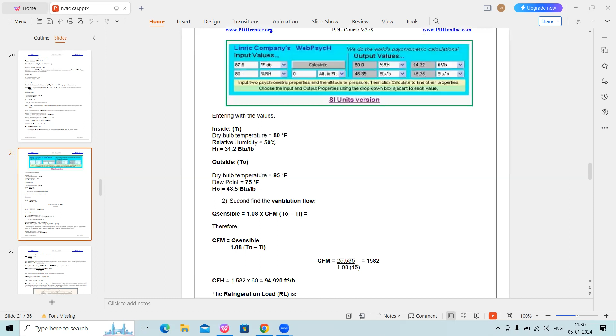Now, second, let us find our ventilation flow. From the sensible ventilation point of view, Q sensible is 1.08 into CFM into T naught minus TI. In that, the unknown is CFM. So CFM equals Q sensible by 1.08 into T naught minus TI. Q sensible already calculated is 25,635, and 1.08 into 95 minus 80, that is 15 degrees Fahrenheit. That value of CFM is almost 1582, cubic feet per minute.